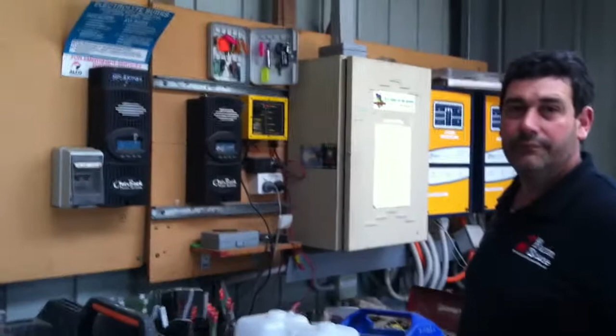I noticed last night, maybe you can talk about the alarm system you've got set up. If for some reason the battery bank gets too low in terms of power levels, and the generator should kick on but for whatever reason doesn't auto-activate and auto-start, you get an alarm and an automatic phone call on your cell phone to come out and check the system. In fact, that happened last night, so maybe you can talk a bit about that too.